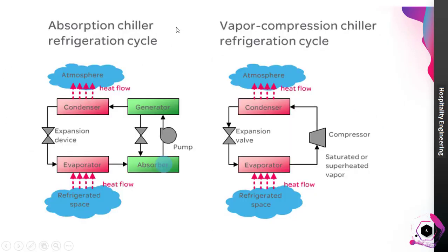Comparing the absorption chiller refrigeration cycle with the vapor compression chiller refrigeration cycle: in the absorption system, the generator, pump, and absorber — shown in the green area — replace the compressor used in the vapor compression system. The compressor is replaced by the generator, pump, and absorber in the vapor absorption system. All remaining components of both systems are similar.